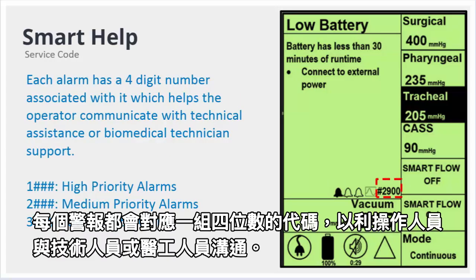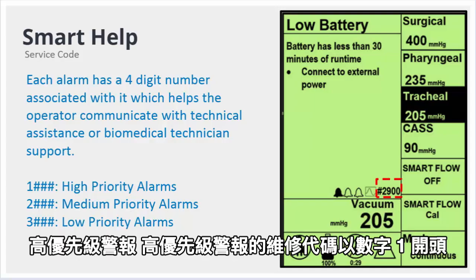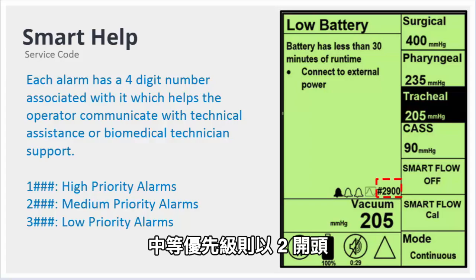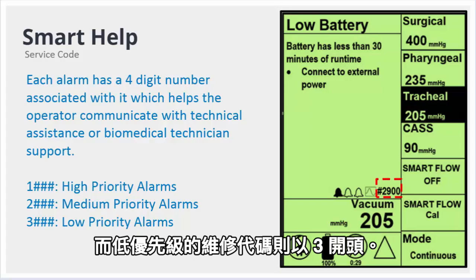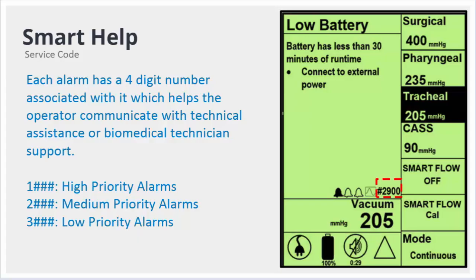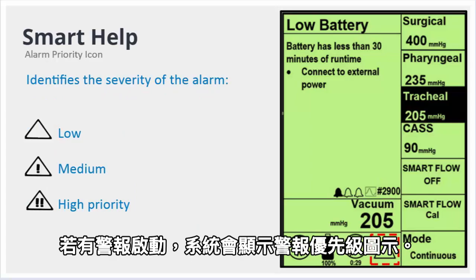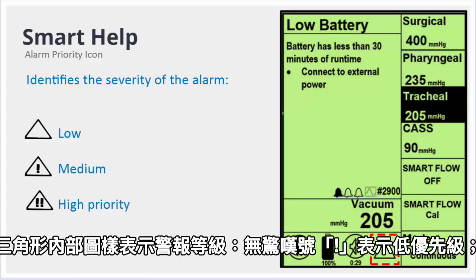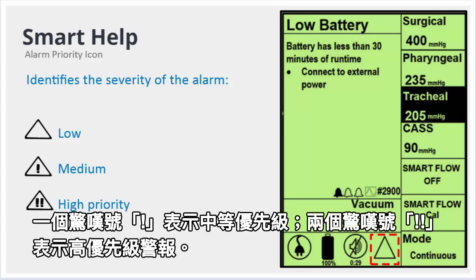Each alarm has a 4-digit number associated with it, which helps the operator communicate with technical assistance or biomedical technician support. A high-priority alarm service code begins with a 1. A medium-priority alarm service code begins with a 2, and a low-priority alarm service code begins with a 3. The alarm priority icon displays if there is an active alarm. The priority of the alarm is indicated by the interior of the triangle. No exclamation point represents a low priority alarm. 1 exclamation point represents a medium priority alarm, and 2 exclamation points represent a high priority alarm.